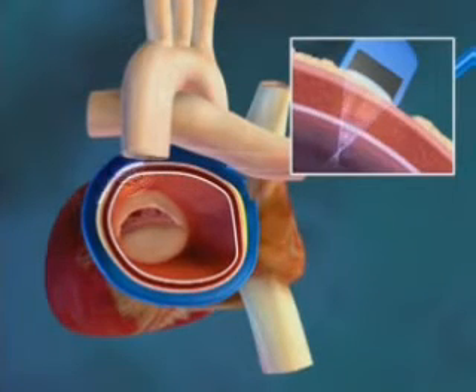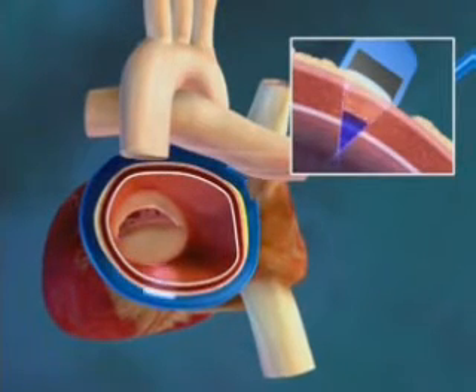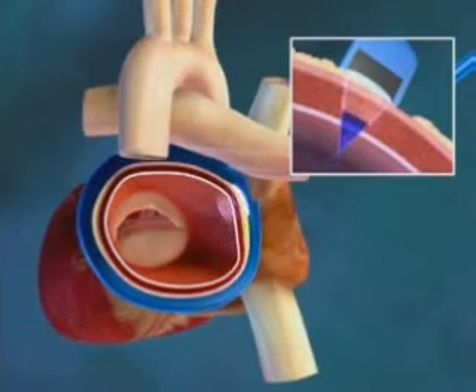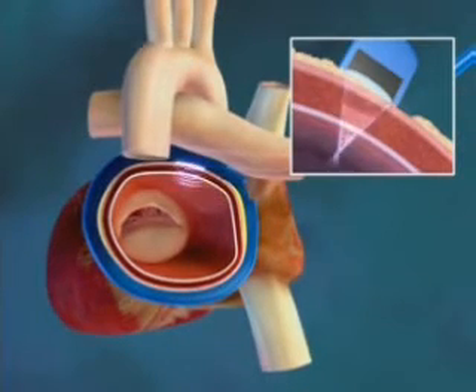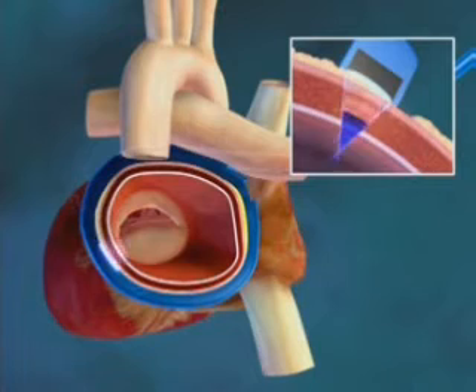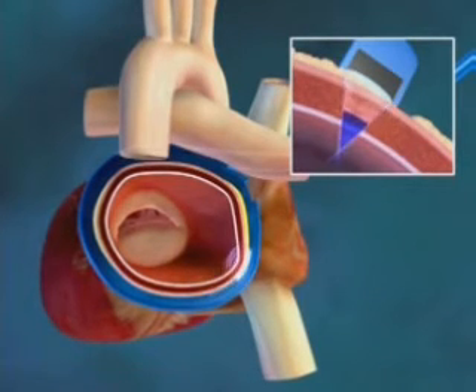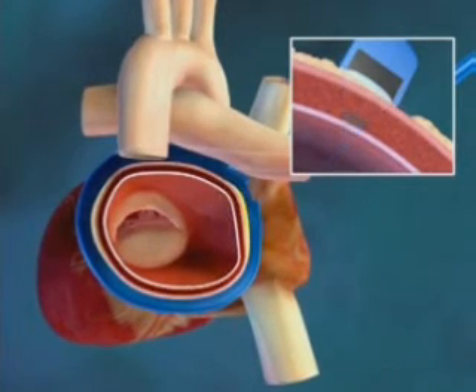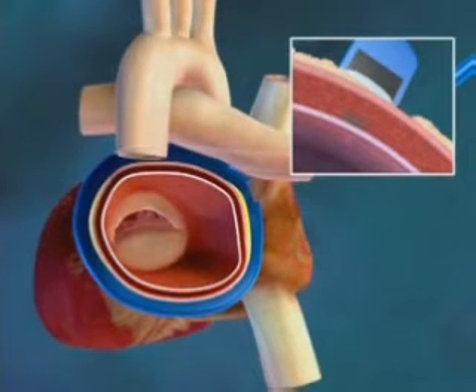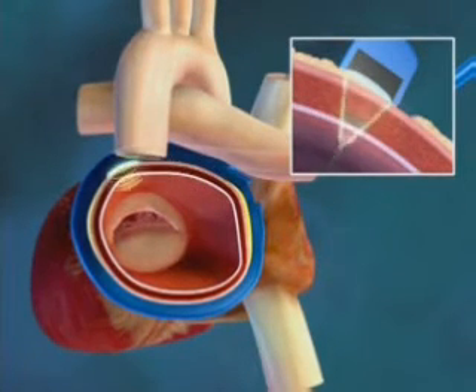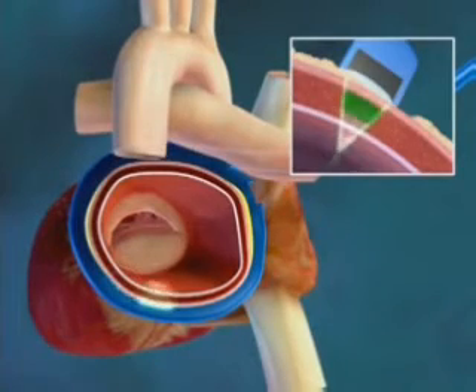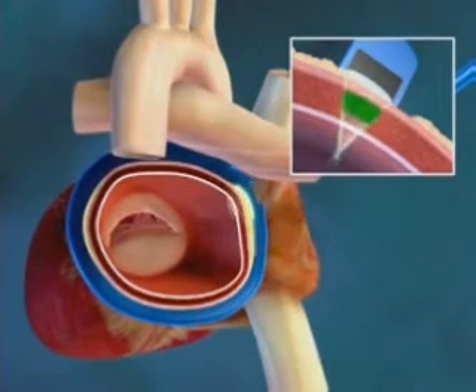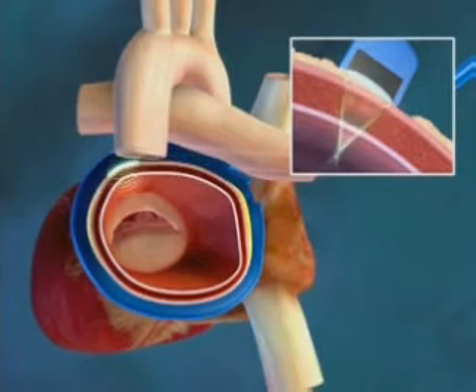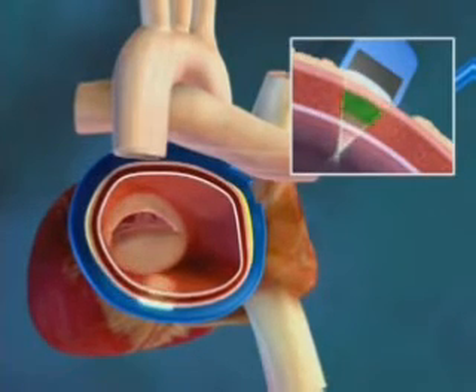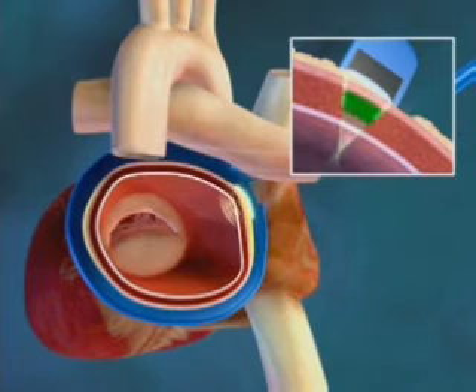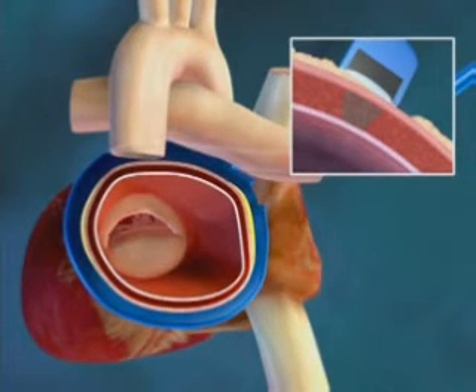During the deep ablation cycle, targeted energy is deposited distal from the transducers into the endocardial zone. Beyond the focal point, the energy dissipates within the left atrial cavity. After circumferential deep ablation, targeted energy is directed to the mid-myocardial layer. Again, circumferential ablation is focused in a very sequential fashion around the left atrium. During the first 2 stages, each transducer is activated sequentially, and the energy is pulsed.